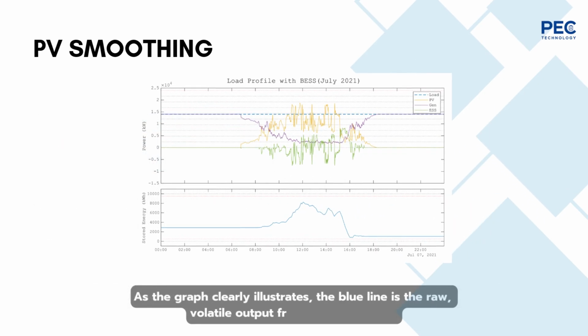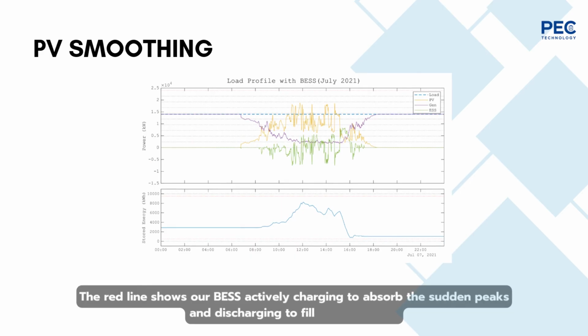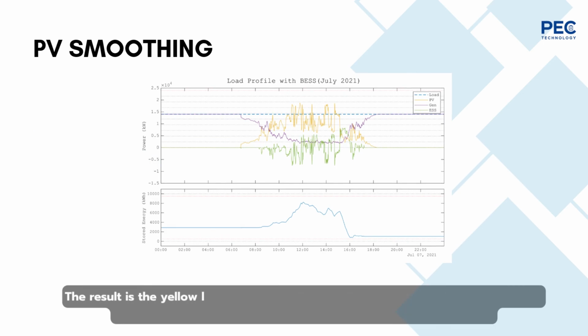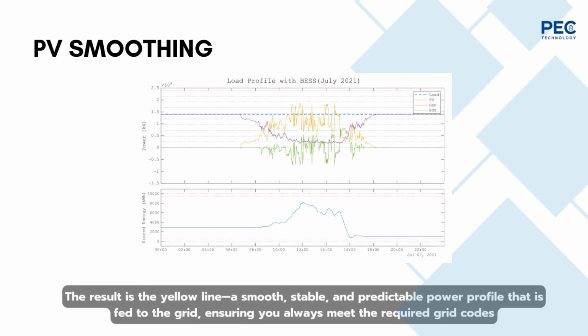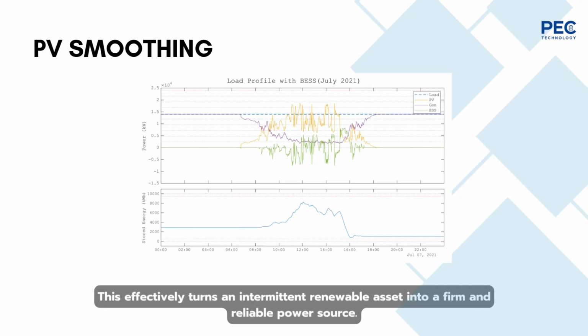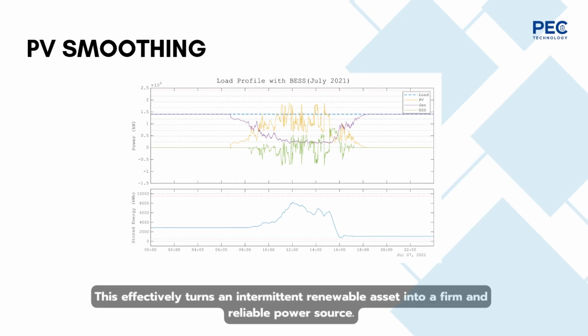As the graph illustrates, the blue line is the raw, volatile output from the solar panels. The red line shows our BESS actively charging to absorb the sudden peaks and discharging to fill in the troughs. The result is the yellow line, a smooth, stable, and predictable power profile fed to the grid, ensuring you always meet the required grid codes. This effectively turns an intermittent renewable asset into a firm and reliable power source.